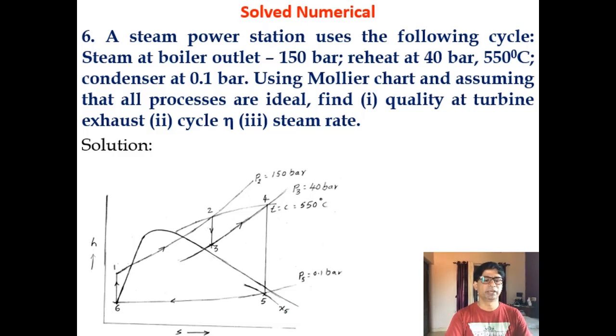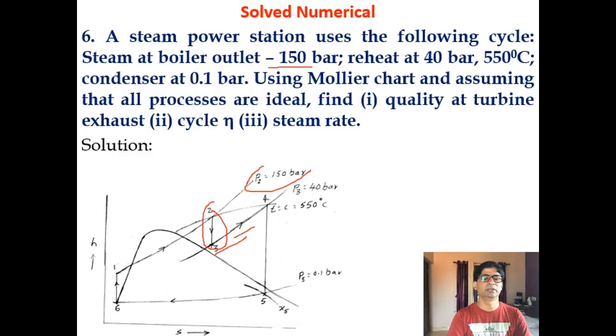This is the Mollier chart diagram. Steam at boiler outlet is 150 bar, so that is pressure 1 to 2 — this line at 150 bar. Reheat at 40 bar means there are two stages of expansion. First stage expansion is 2 to 3, and 3 to 4 is the reheat which takes place at 40 bar to a temperature of 550 degree Celsius. So T2 is also 550 degree Celsius, meaning reheated to original temperature.